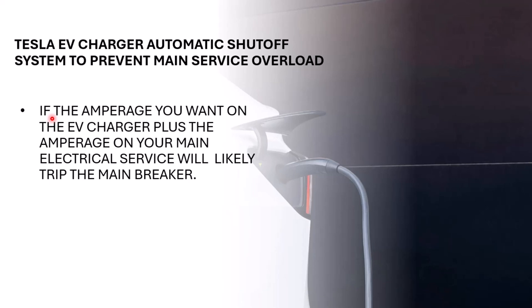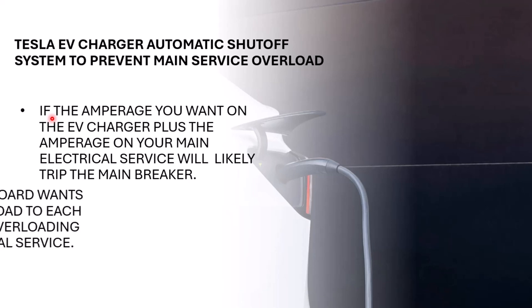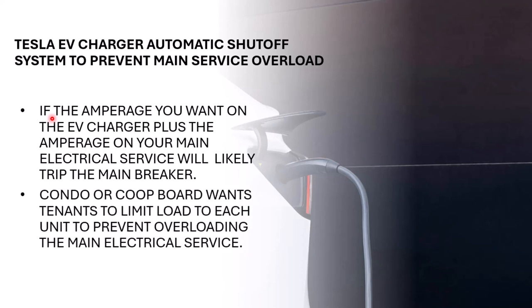So in that case, you may want to provide an automatic shut-off system to automatically shut off the EV charger so the main breaker does not trip. And then when the power goes back down, the system would sense that and then automatically turn the power back on to the EV charger. Another reason is, some condos and co-op boards want the tenants to limit load to each unit to prevent overloading the main electrical service. Because if they were to increase the main service, that would cost a lot of money for the building, and that's something that they may want to avoid doing.